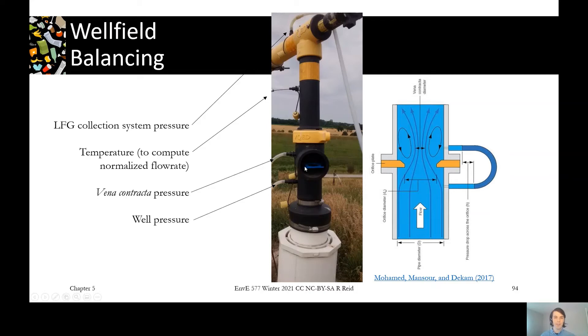On top of this can be, in some wellheads, an orifice plate, which if you think back to second year hydraulics, an orifice can be used as a device with no moving parts to measure the flow of a fluid by looking at the pressure drop through the orifice plate. So that's what's going on in this picture here. The flow is forced through here, it speeds up and then to equalize the energy balance, it changes the pressure and you can measure that.